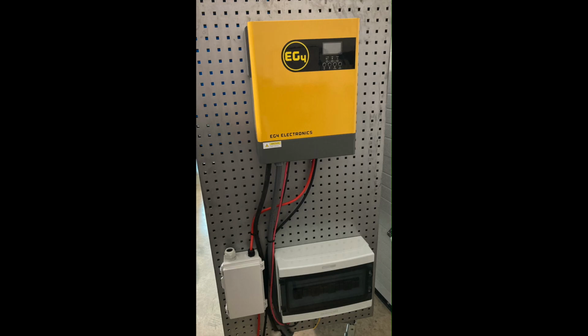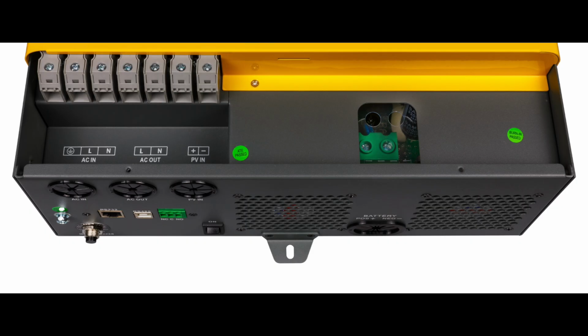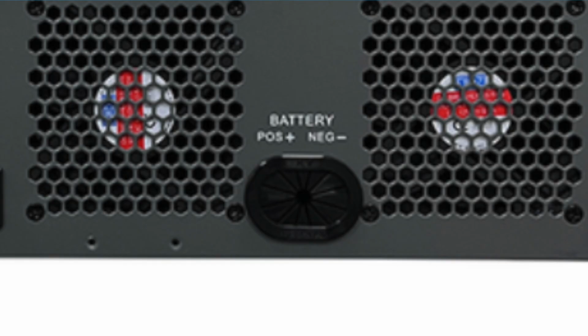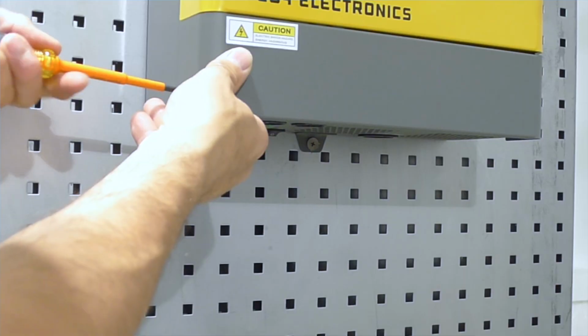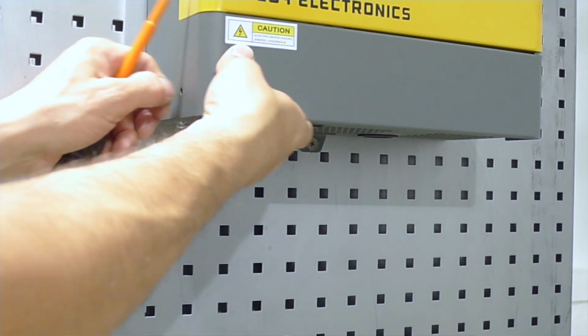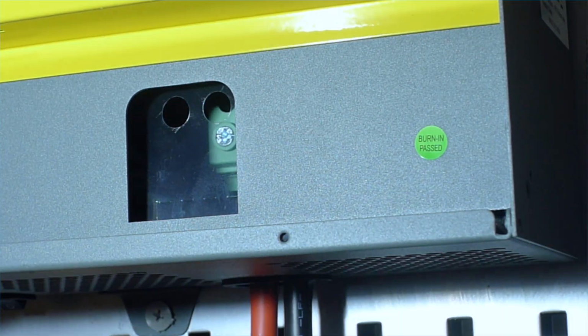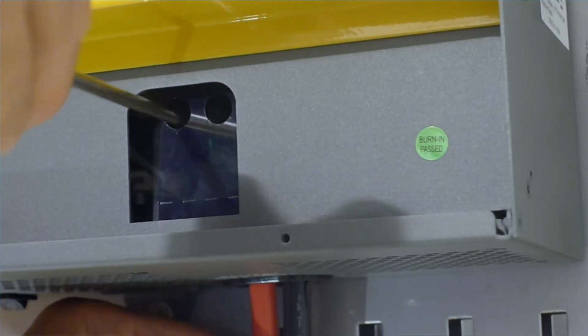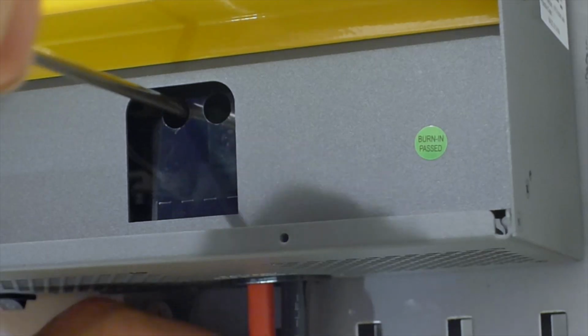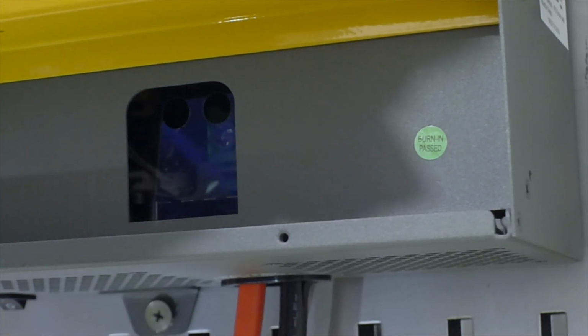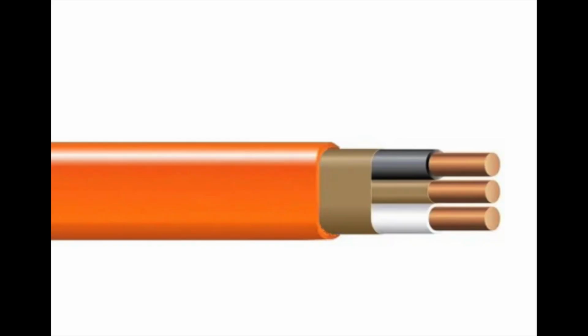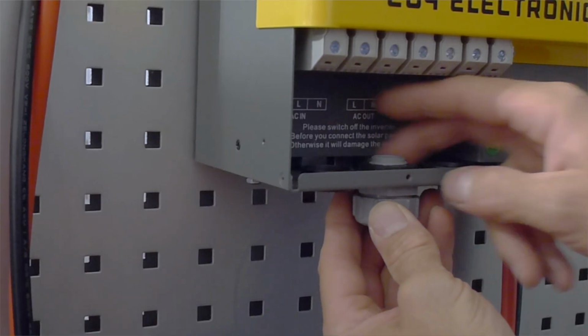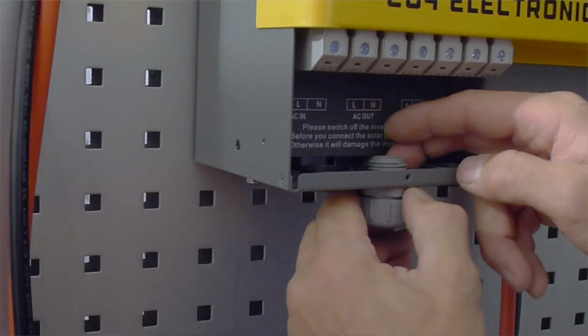We can start wiring the components together. This is a picture of the bottom of the inverter. As we can see to the right, that's where we can connect the battery cables we received in the package. Let's remove the cover and connect the red cable to positive and the black cable to the negative terminal. We are going to use this 10-2 copper building wire for AC out, and right now we are going to install a cable gland first.